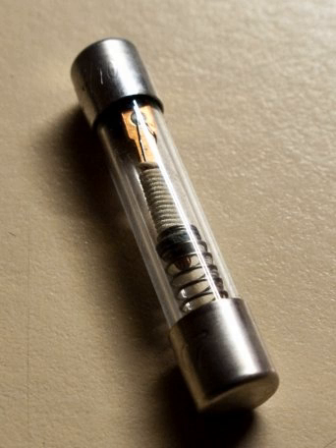Fuses are selected so that the minor, branch fuse disconnects its circuit well before the supplying, major fuse starts to melt. In this way, only the faulty circuit is interrupted with minimal disturbance to other circuits fed by a common supplying fuse. Where the fuses in a system are of similar types, simple rule-of-thumb ratios between ratings of the fuse closest to the load and the next fuse towards the source can be used.